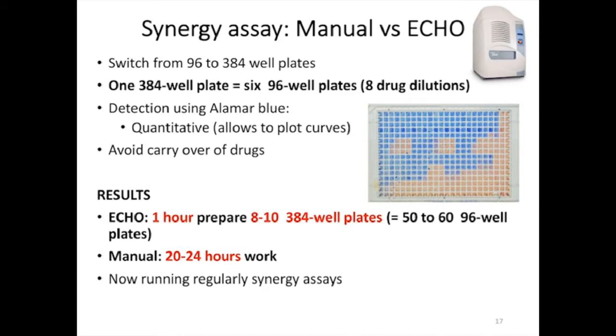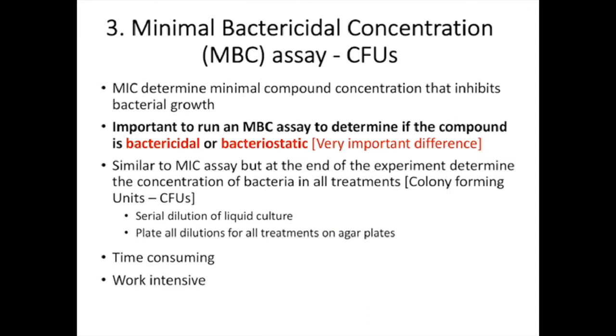And with the Echo we are able to prepare in 1 hour 8 to 10 384 well plates, which correspond to 50 to 60 96 well plates. It will take 24 hours to prepare the same amount of plates manually. So it's been a big advantage, the Echo, for us, because we are now able to run synergy assays regularly, whereas before we were just running them on some occasions.